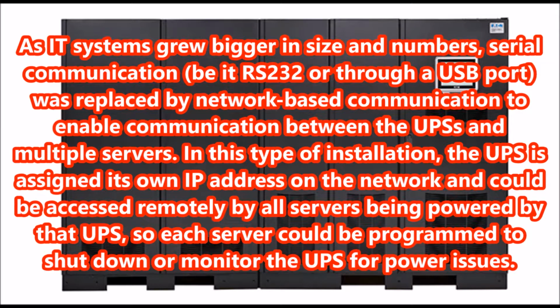As IT systems grew bigger in size and numbers, serial communication, be it RS-232 or through a USB port, was replaced by network-based communication to enable communication between the UPSs and multiple servers. In this type of installation, the UPS is assigned its own IP address on the network and could be accessed remotely by all servers being powered by that UPS, so each server could be programmed to shut down or monitor the UPS for power issues.